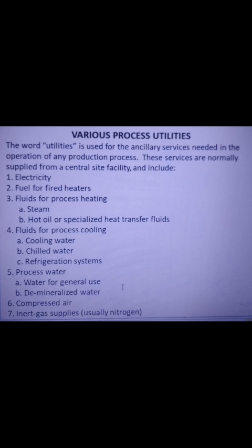Now I will tell you about the steam. Steam is the most widely used heat source in chemical plants. Steam has a number of advantages as a hot utility. The temperature at which heat is released can be precisely controlled by controlling the pressure of the steam. This enables tight temperature control, which is important in many processes. Condensing steam has very high heat transfer coefficients, leading to cheaper heat exchangers. And steam is non-toxic, non-flammable, and visible if it leaks externally.